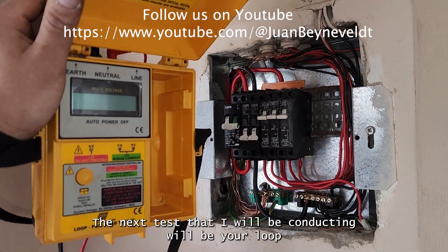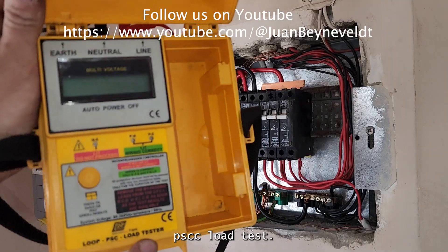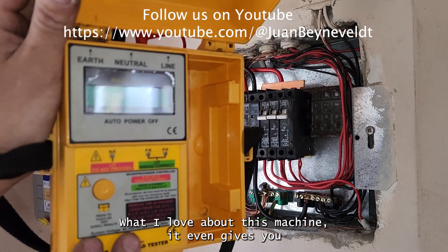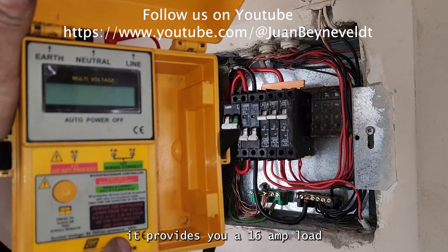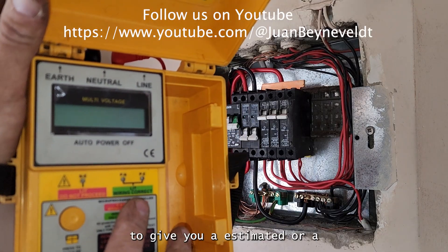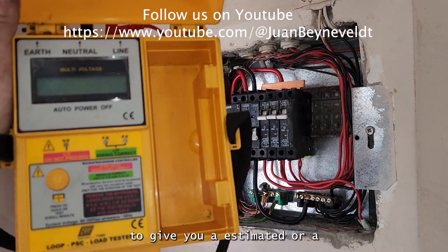The next test I'll be conducting will be using your Loop PSC Load Tester. What I love about this machine is it provides you a 16 amp load to give you an estimated mock-up volt drop.